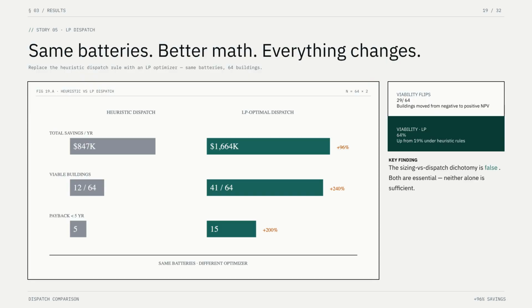Story 5. Same batteries, we just replaced the rule-based charge-discharge heuristic with a linear programming dispatch optimizer. Portfolio savings nearly double, from $847,000 to $1.66 million per year. That's a 96% improvement with 0 additional hardware. 29 buildings that were losing money become profitable. Viability jumps from 19 to 64%. The sizing versus dispatch dichotomy the literature frames as a trade-off, it's false. Both are essential.